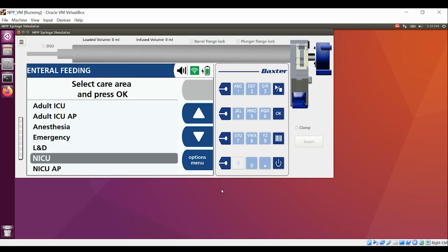We offer loading and bolusing, of course, on our pump, just like on the LVP, and you'll see it used throughout the hospital. But in the NICU, you may see that their practice is to set up a separate pump for a loading dose and or set up a separate pump for a bolus dose. They may not necessarily run it off of the continuous infusion. So just wanted to point that out to you, just in case you come across that. Of course, it's more efficient to set up the loading dose and deliver from the continuous infusion or deliver a bolus dose from the continuous infusion because it goes right back to that continuous infusion.